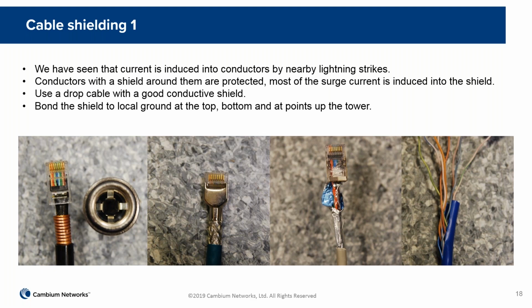These are quite difficult cables to make effective connections to. The aluminium is difficult to make a reliable long-term connection to, and the drain wire itself is low current and fiddly to deal with. So not a good solution. And then on the right we have an unshielded pair, which I'm afraid just doesn't provide us with any way of carrying away the surge current. So really we're looking at the two methods on the left here.